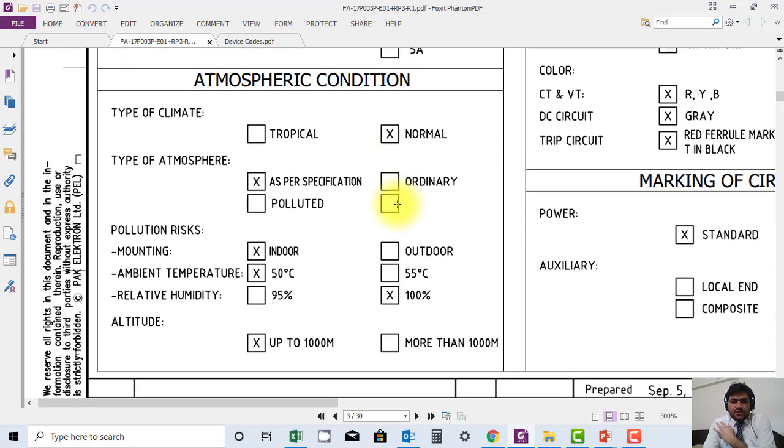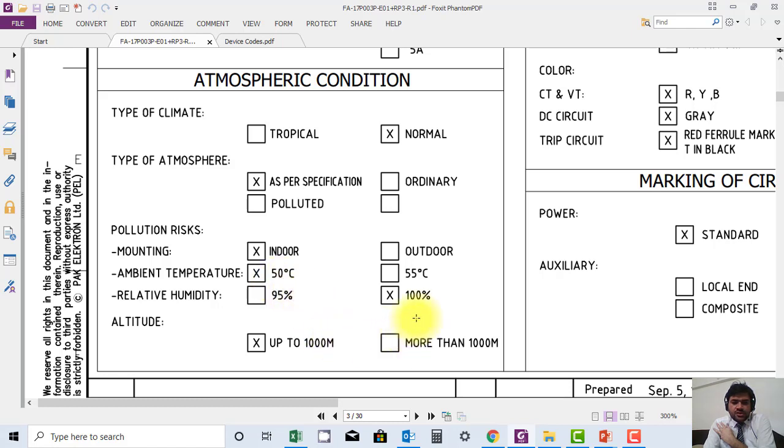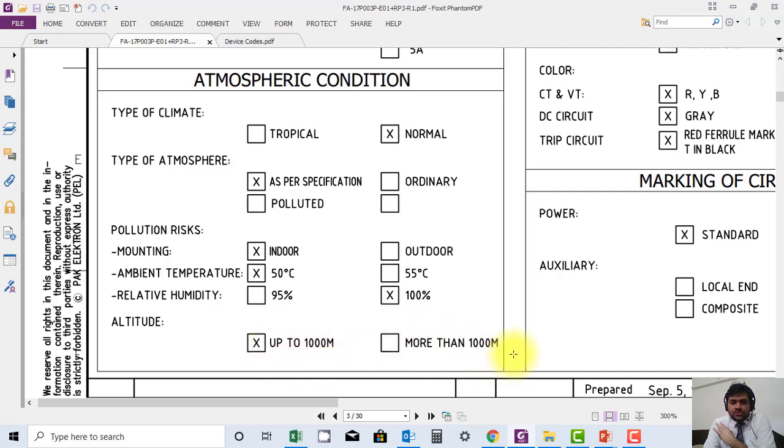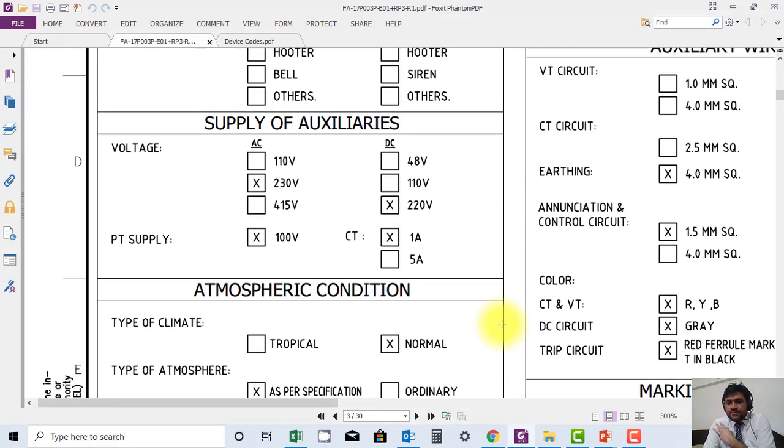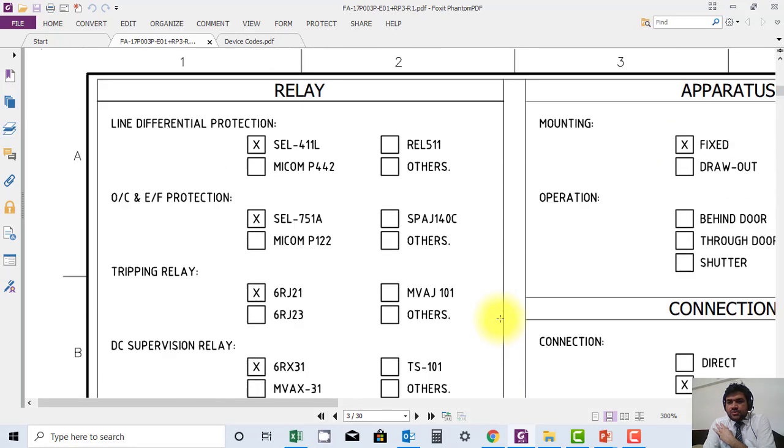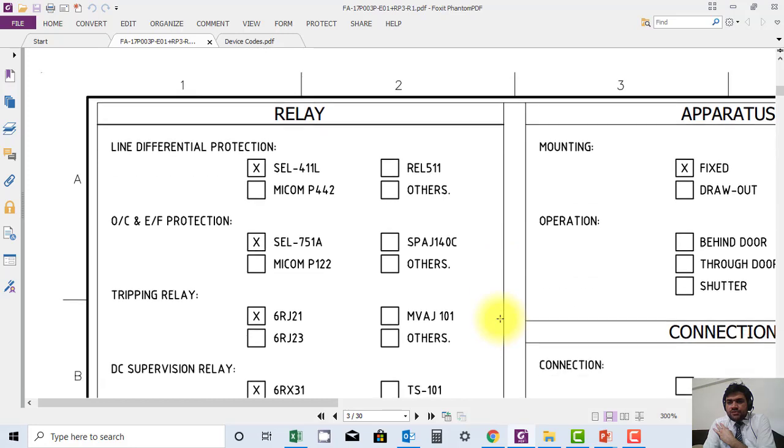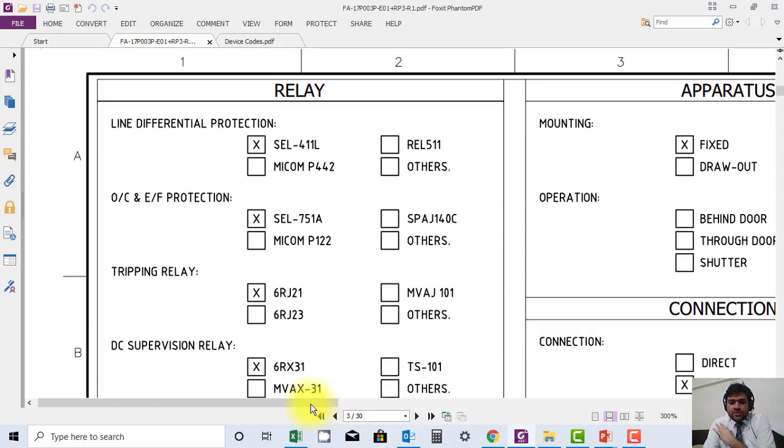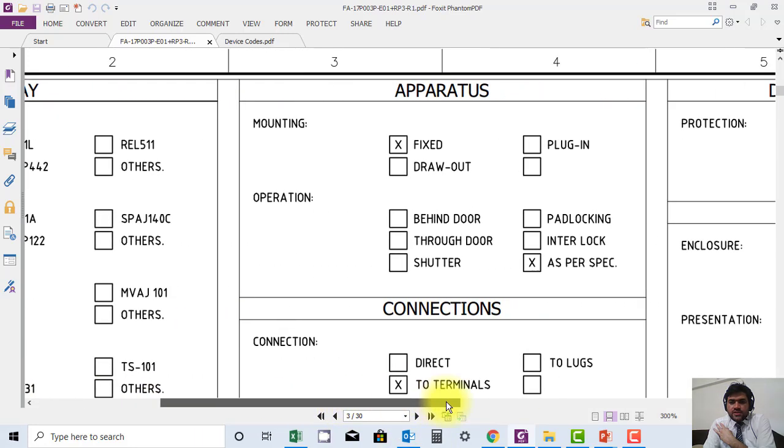These are such things: the pollution risk, mounting is indoor, and ambient temperature specifications. It can work at humidity 100 percent, it can sustain altitude up to 1000 meters. So this type of general information is very useful.